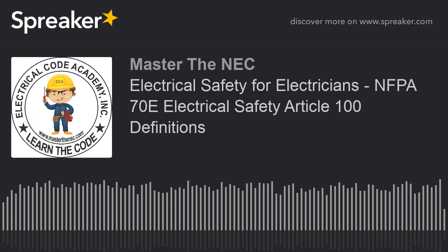Again, this is an example under the informational note that I love because it gives us something we can really sink our teeth into, so read the informational note. It says, injury and damage to health resulting from shock is dependent on the magnitude of the electrical current, the power source frequency, whether it's 60 hertz, 50 hertz, or what have you, and the path and time duration of current through the body. So the level of current, the number of amps, and the frequency, 50 hertz or 60 hertz. In most of our cases it'd be 60 hertz, which is very much the same frequency as the signals to the brain.